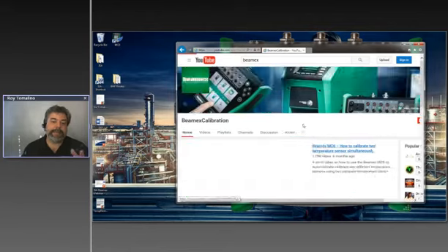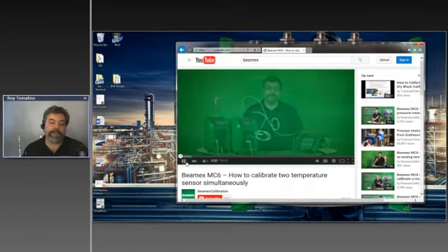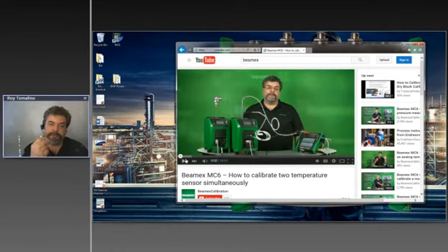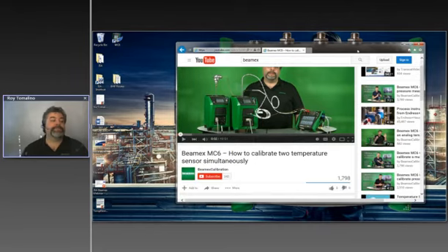In this example, this is a video of how to calibrate two different sensors at the same time. This is using two thermocouples. No, it's not. Two dry blocks. We're testing a thermocouple and an RTD. These could be going to the same transmitter as a dual sensor, but this example is testing the two elements themselves. So we're calibrating a thermocouple and an RTD using one calibrator with the push of one button, because the entire thing is automated. And you can check that out by simply going to YouTube.